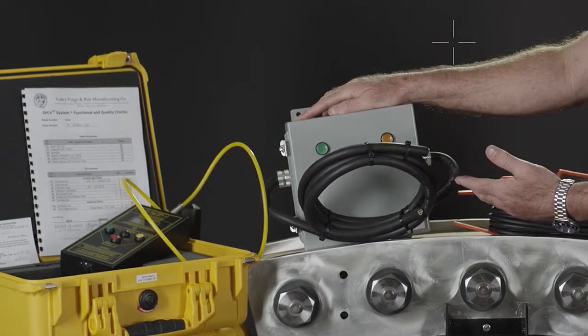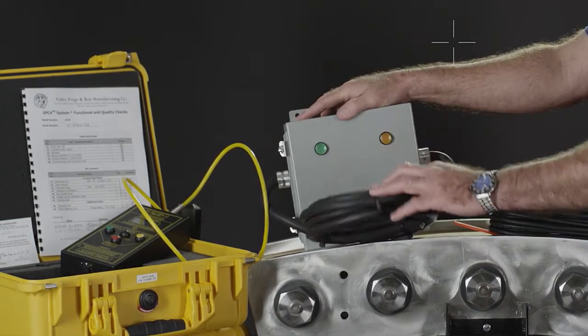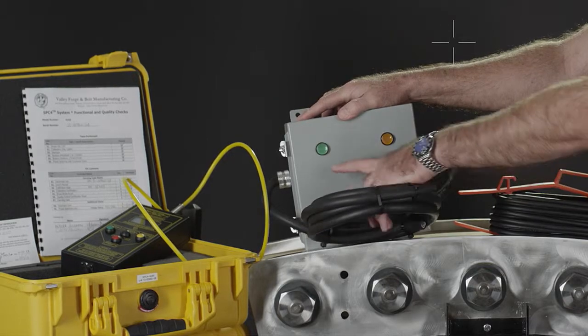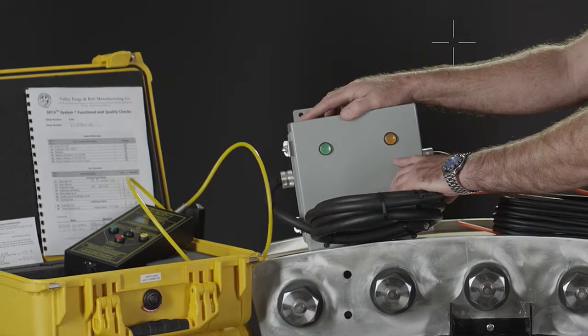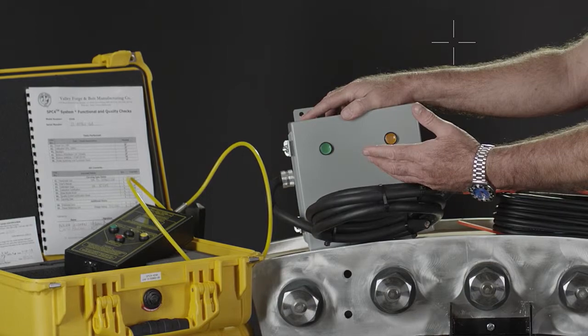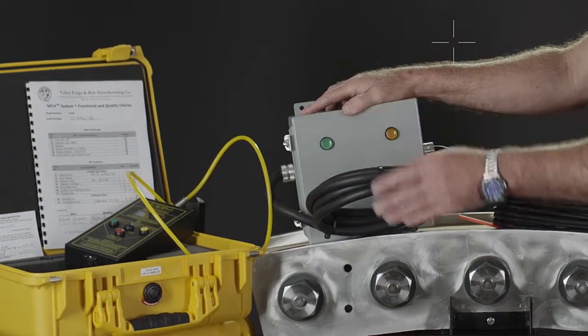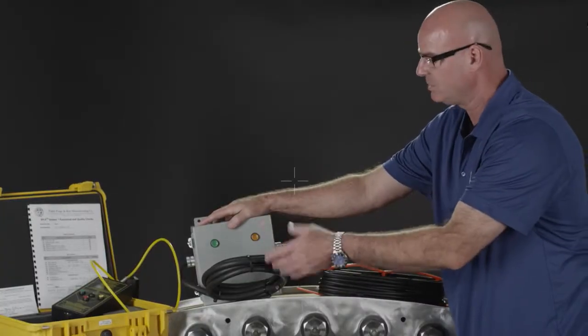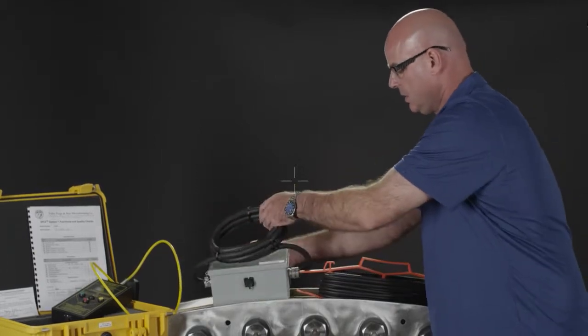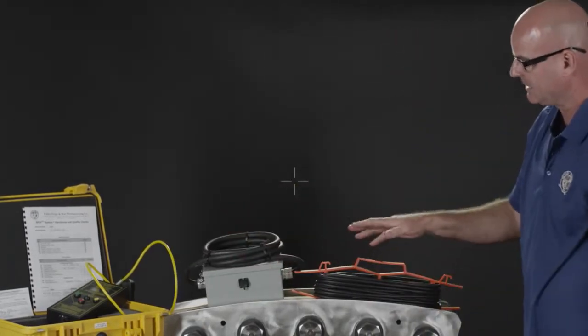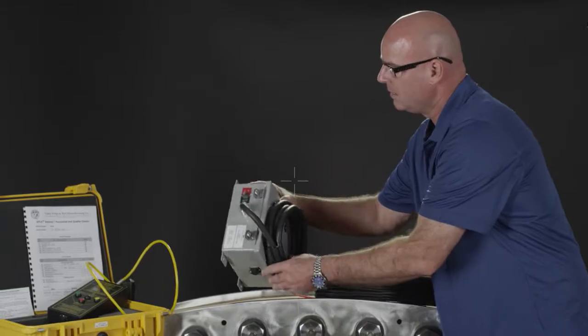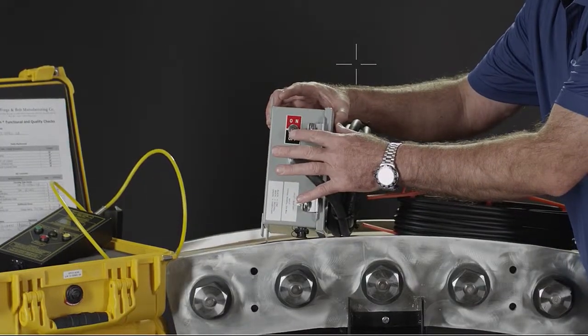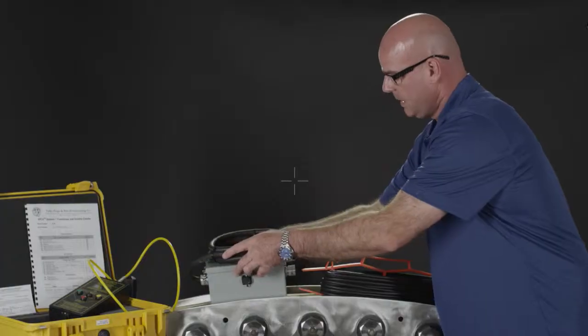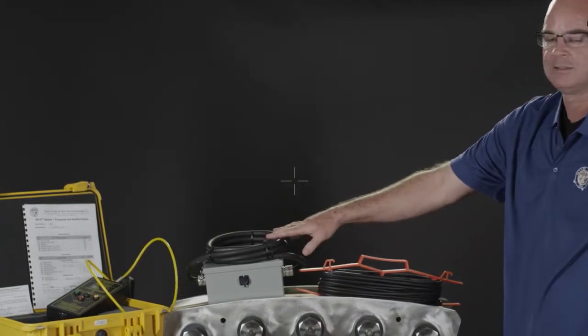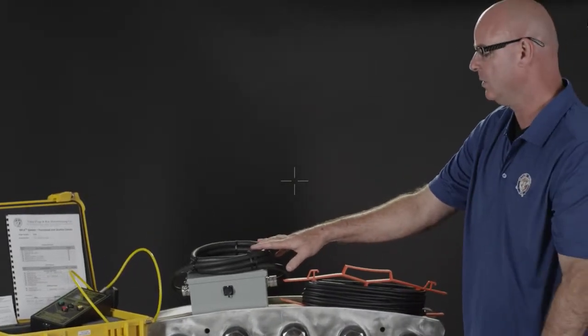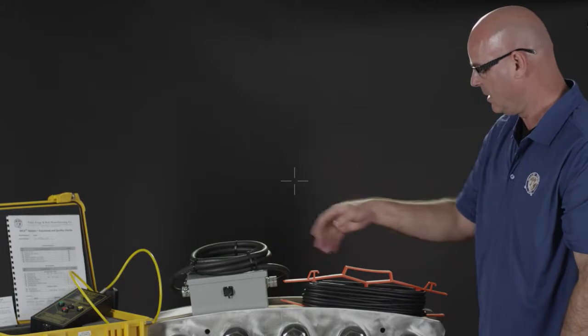Comes in 110 or 220 volt. It's got a green lens or a green light and an orange amber light that shows you where it's at as far as power going to the meter. And we're going to display that and demonstrate that here shortly. So that's the gray box that connects it. It's got a circuit breaker on it right here that allows you to turn it on and off. You have to supply the cable ends to whatever you're connecting into your power source at your site.